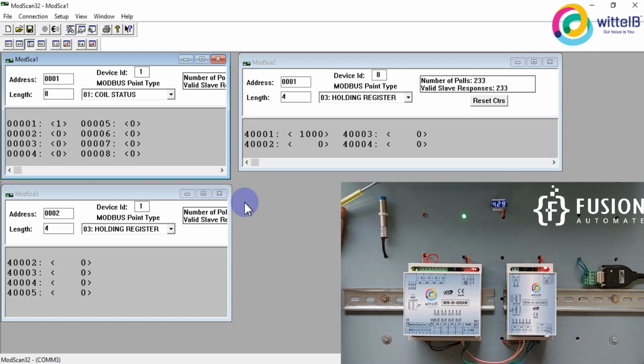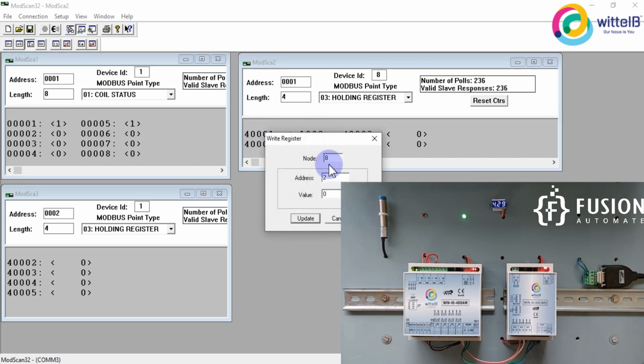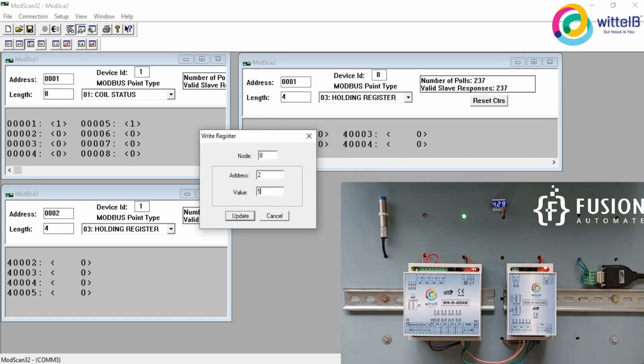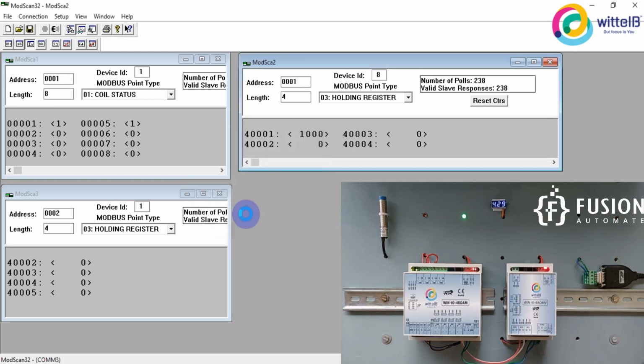If I remove my screwdriver, then it will show status as 1, because it is providing 12 volts to this card. And if I increase some voltage here, like 500, I'm providing the raw value, but whenever I provide a raw value to this AO2, it will convert into voltage. And that voltage is directly linked with the AI1, so you will see some proportional change in this analog input channel. So this is how you can test this Modbus IO card.